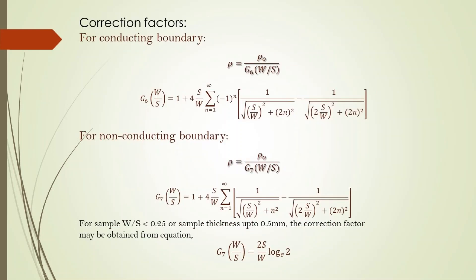After obtaining ρ₀ using the equation ρ₀ = V/I × 2πs, this is not yet the correct value — some corrections must be incorporated. This is because we assumed the material is semi-infinite, meaning the thickness should be large compared to probe spacing and the lateral dimensions should also be large compared to probe spacing. However, in practice we will use thin samples, so geometrical corrections must be applied.